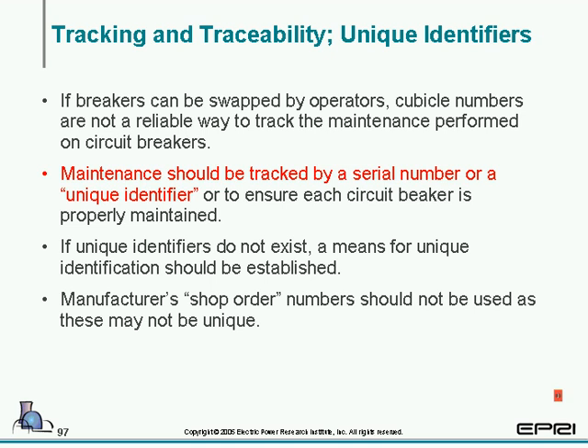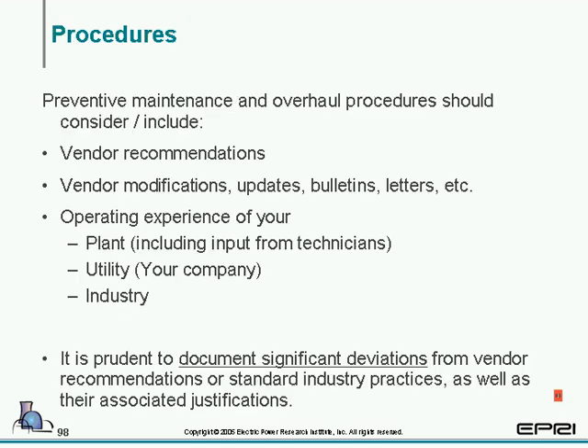Now, what you want to be careful of is tracking breakers by their cubicle number. I know in my plant, a fossil plant that I worked at, we tracked maintenance by the cubicle. And it is possible in many, or I would say most plants, that operators have the ability to swap out breakers for operational purposes. If they swap a breaker, then you've lost your maintenance record. So a key thing is maintenance should be tracked by serial number or unique identifier. If they don't exist, you should probably create one if you want to properly track your maintenance of each individual circuit breaker. We also learned somewhat the hard way that shop order numbers should not be used, as shop order numbers may not be unique.